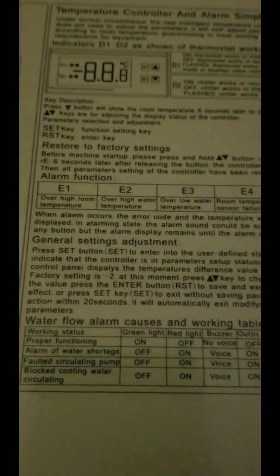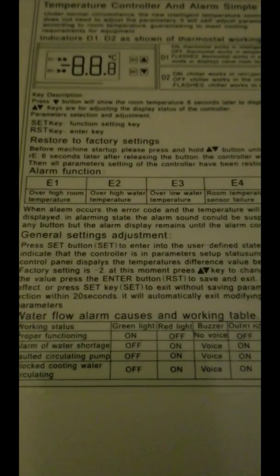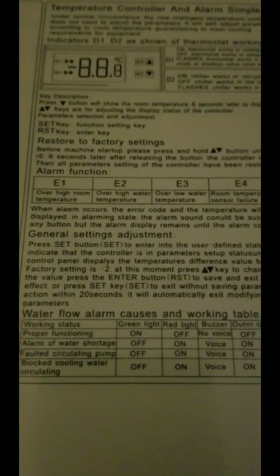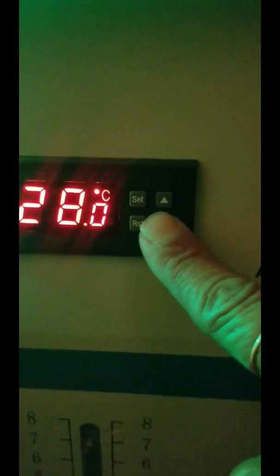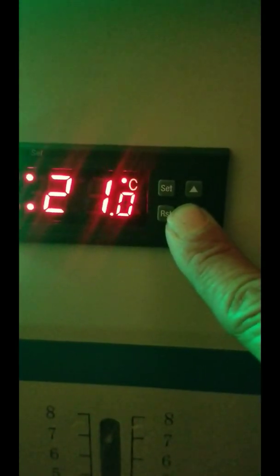Normally, the top of the machine has some basic instructions. If you just want to go off the defaults and change the temperature, you press SET, enter the value you want, and then press RST to save it. So if we press SET, we can go down — let's say we want 20 degrees — and then press RST to save it. So it should be saved.